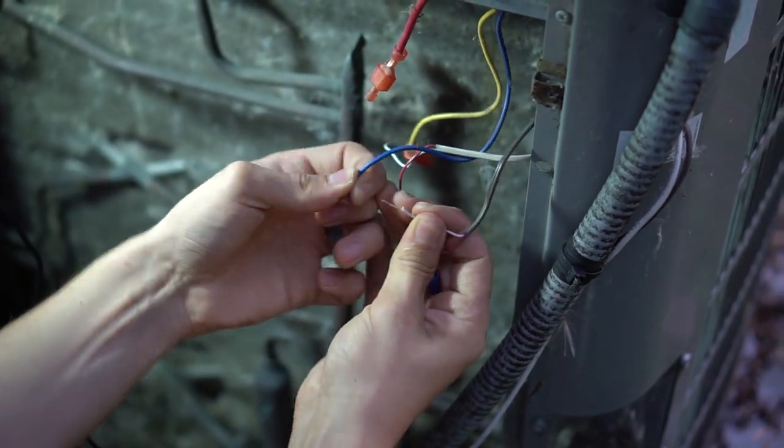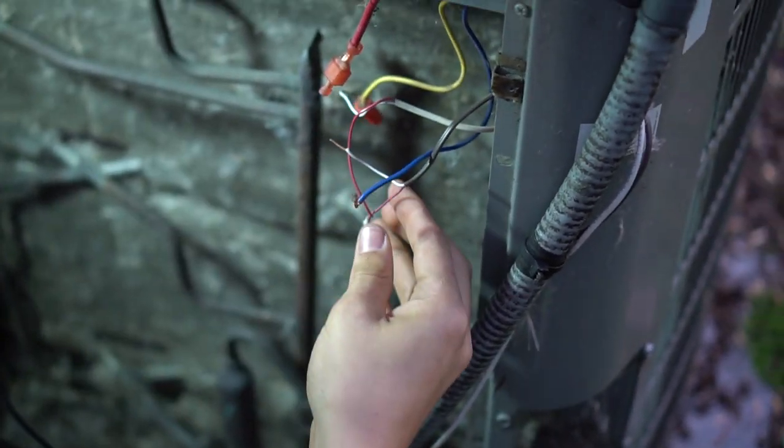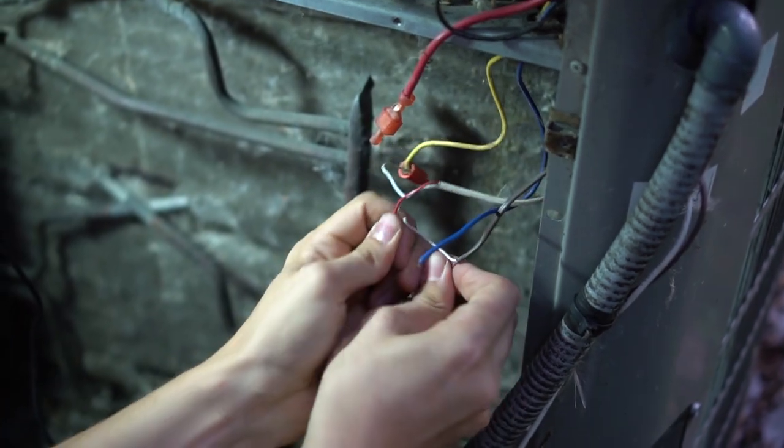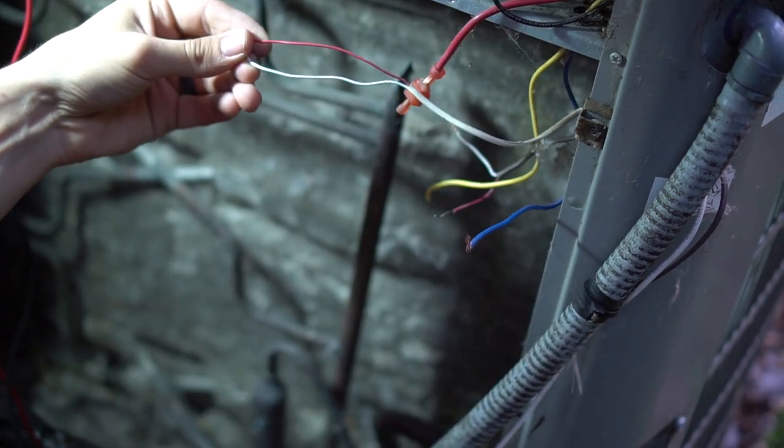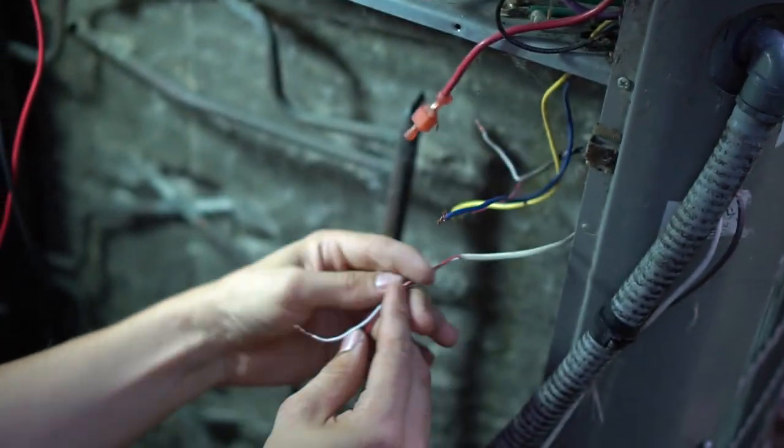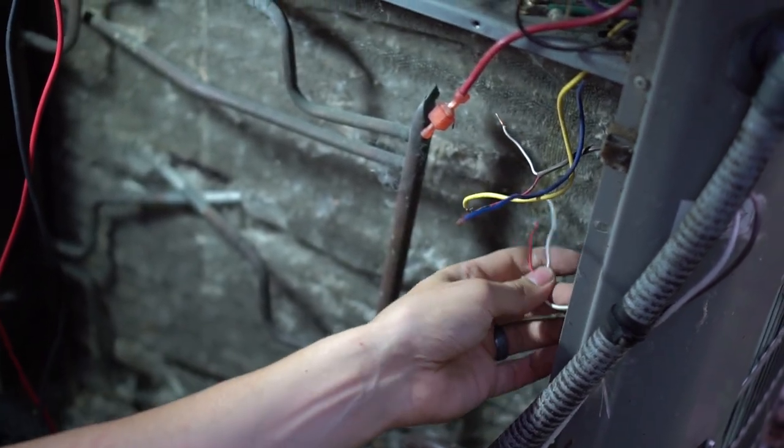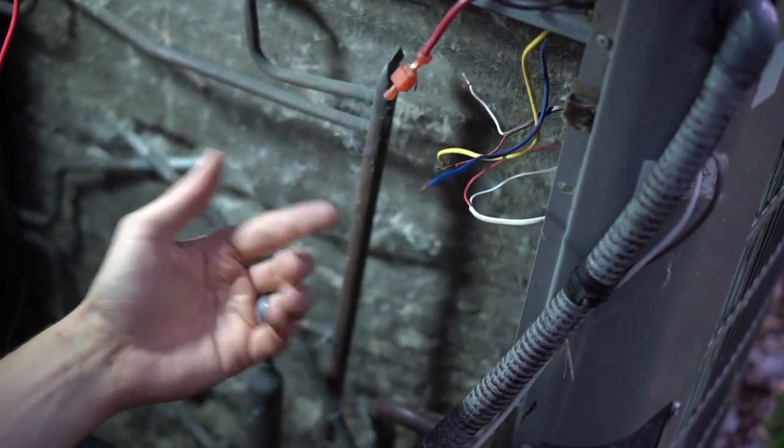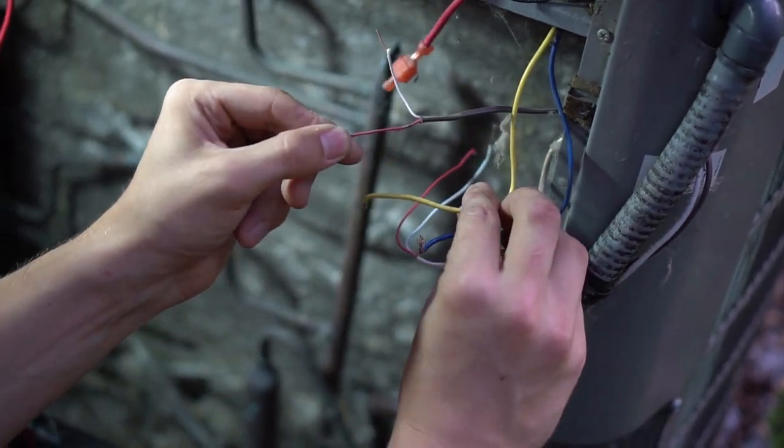So disconnect all your wires, all the wire nuts I mean, like such. So once you've got your wire nuts off, here's the thermostat wire going to your power saver switch. We're simply going to take it out of the circuit. You can either put some wire nuts on it, tape it, or just move it out of the way. Make sure it's not touching any metal just in case. It shouldn't have any voltage going there because what supplies the voltage is the brown thermostat wire right here.